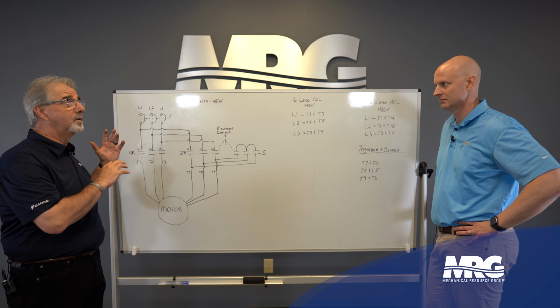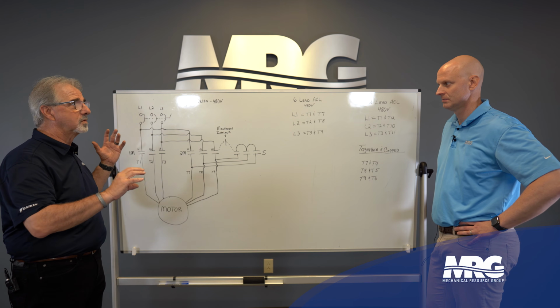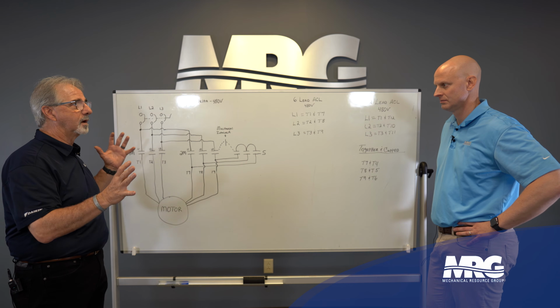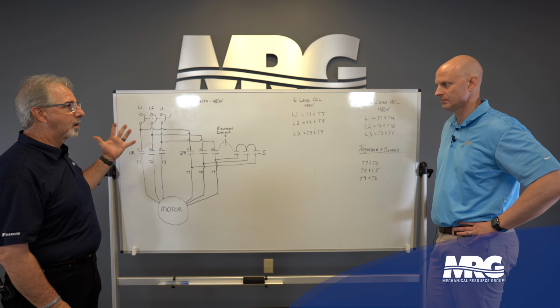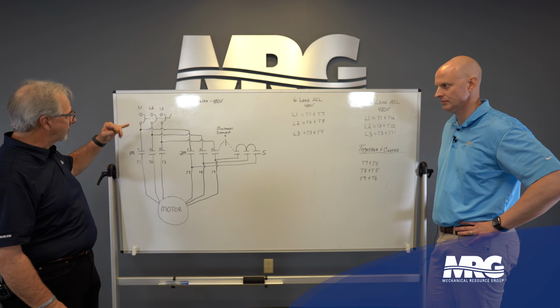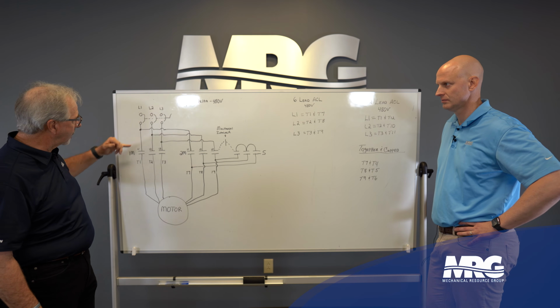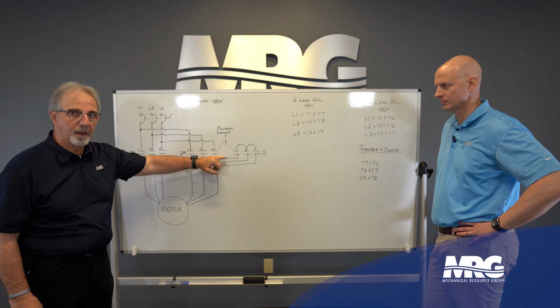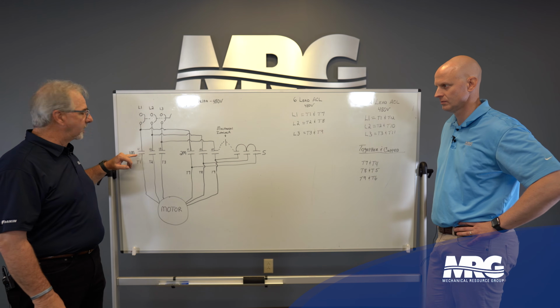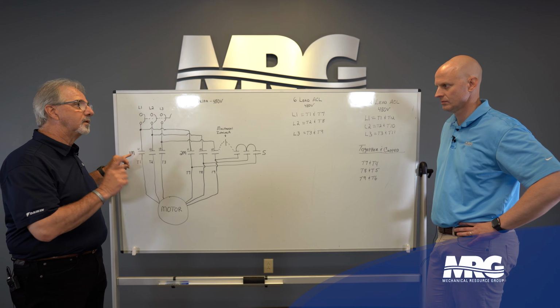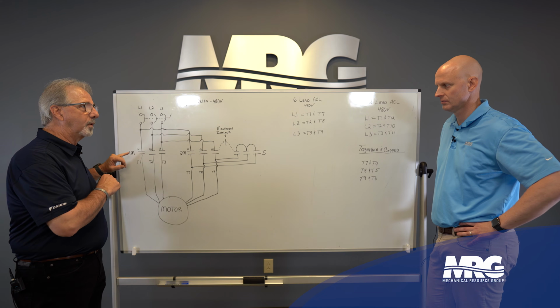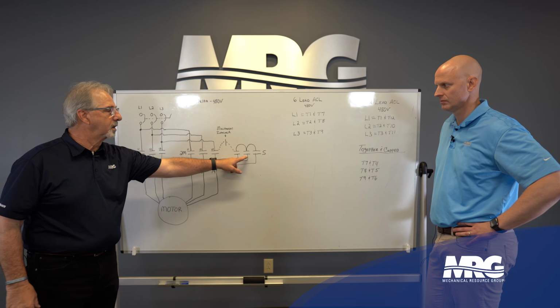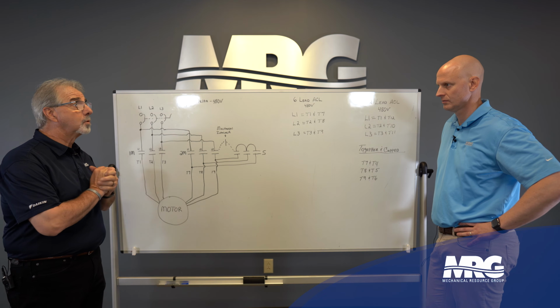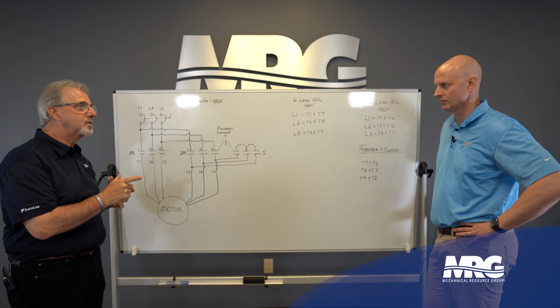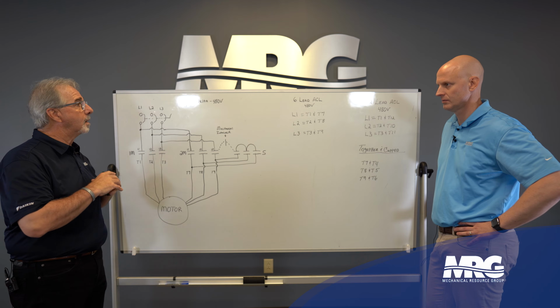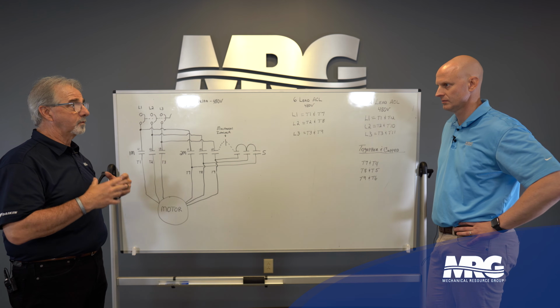Now I have a definite differentiation inside the motor between the Y and the Delta, okay? So we start on the Y, and again, like I was saying, this is your main circuit breaker, and if you'll notice we have 3 contactors that go across here. The 1M contactor is going to come in, but in this case, John, like the part winding, we're also going to bring in the shorting contactor because I need to short the Delta. Now what this does is it gives me a much better reduced voltage performance.